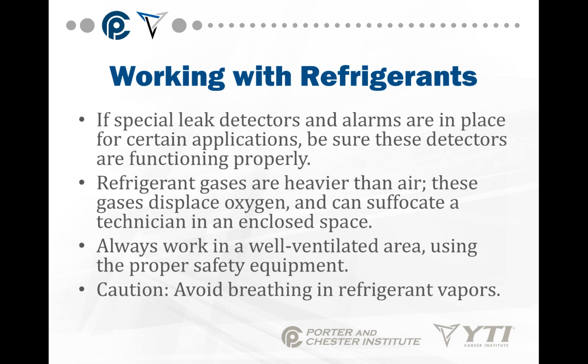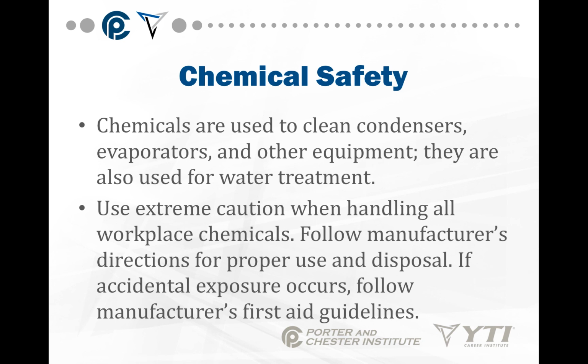If there are special leak detectors and alarms in place for certain applications, make sure these detectors are functioning properly. Refrigerant gases are heavier than air. The gases displace oxygen and can suffocate a technician working in an enclosed space. Always work in a well-ventilated area and use proper safety equipment. Do not breathe in refrigerant vapors.